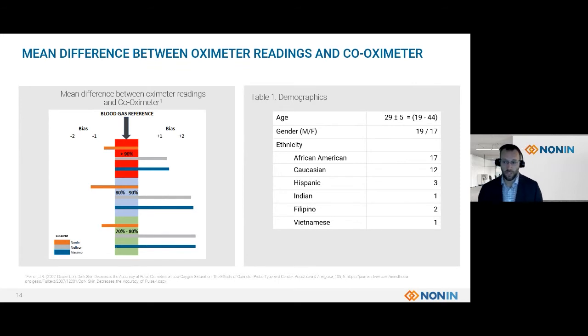So all co-oximeters read slightly differently, all different brands. So the only true way to have an apples to apples comparison of pulse oximetry technology is to compare devices against the same subjects with the same co-oximeter. The information that I'm going to be presenting today is based off a peer-reviewed published study with the three major oximetry manufacturers, including Nonin, with a variety of subject demographics, as you can see on the right. These were compared from actual blood gases and compared to the measurements with our pulse oximeter.